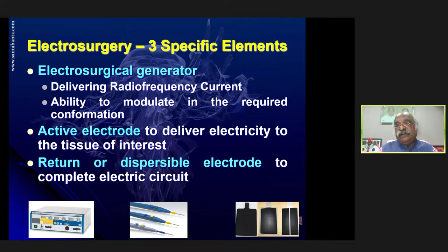Now, the electrosurgical generator, I said, should have different types of current and modulation. So what are the different types of current? In an electrosurgical generator, one is monopolar current. A generator should have a monopolar current output. I remember it started from the 1970s. Monopolar current was commonly used, and it has a tissue effect. We know the benefits of this, and we'll discuss it.